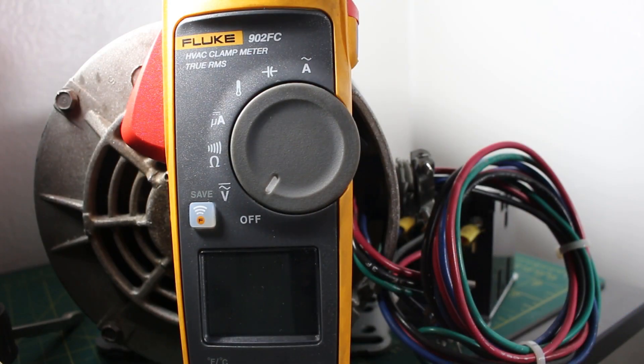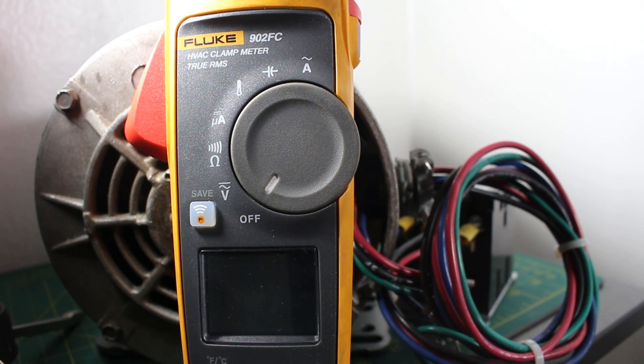For the most accurate reading you're going to want to use a megohmmeter, but with today's technology it's not exactly needed. Today I'm going to be using a multimeter — the Fluke 902 FC HVAC clamp meter. We're going to be checking the resistance of this motor and we're also going to be checking for any grounds.